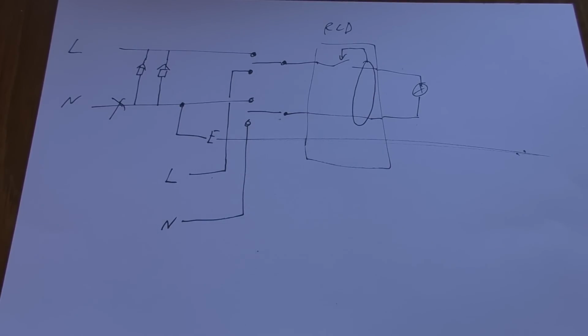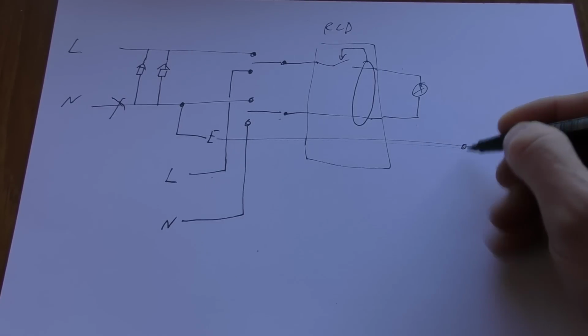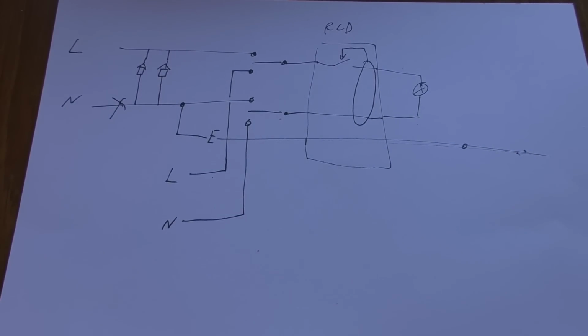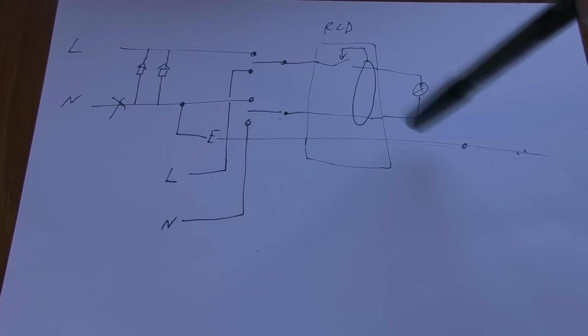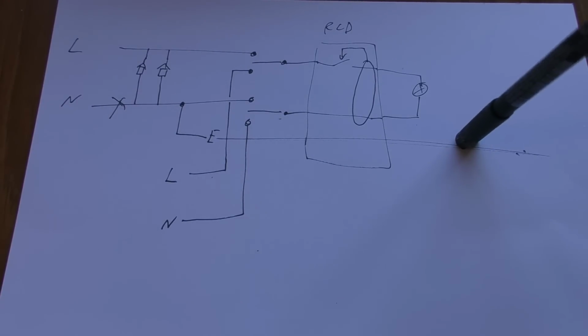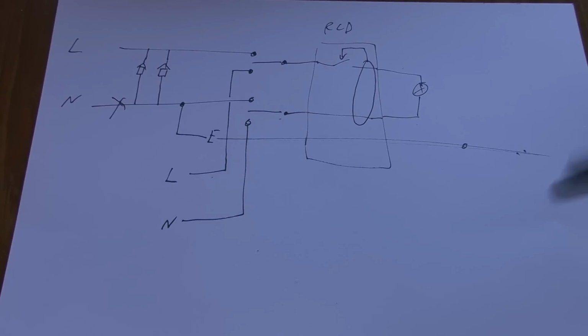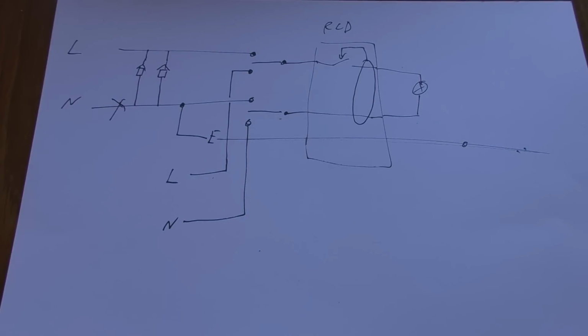Now that may sound terrible and horrific, but actually the way that the electrical systems in houses are designed is that everything within that house, for example the water and the gas services, are bonded onto this earth. It's called equipotential bonding. So even in a fault situation where your earth that's running around your house is at mains voltage, there isn't really access to a true earth inside the house. So if you touch it, you're going to be at mains voltage, but because everything else is bonded to this, for example if you're in the bath, that bath is bonded too, so you and the bath and the water will all be at mains voltage, but there won't be anything to actually close that circuit to allow current to pass through.